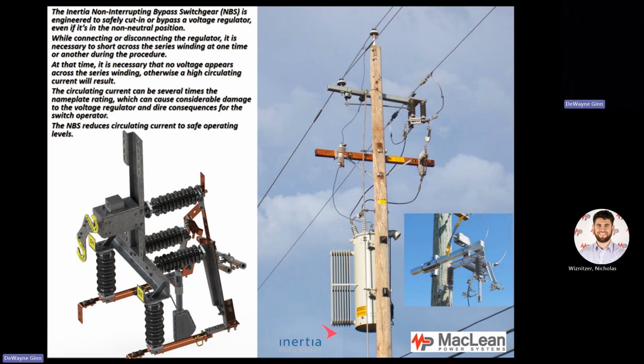If you cannot get it in neutral to take it offline, and there's a reason to take it offline, if all of a sudden it's becoming damaged and needs to be repaired, the utility is trained to take an outage to take it offline because it is a dangerous piece of equipment. Now, the non-interrupting bypass switch was developed over 50 years ago to safely take it offline without having to take an outage and affect reliability.